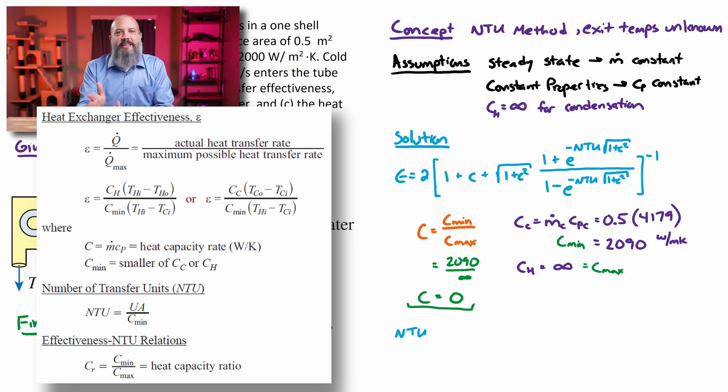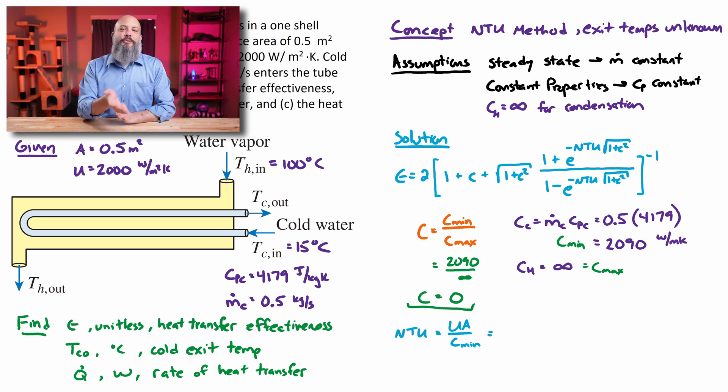So NTU, number of transfer units, is a ratio between UA and CP. Think of the heat transfer equations: M dot CP delta T and UA delta T. Those delta T terms are different. For M dot CP delta T, it's the temperatures within a stream, like inlet versus outlet. For UA delta T, you're comparing the two temperatures that are right next to each other. But NTU is a ratio of the front parts of these equations, UA versus M dot CP. And specifically, the M dot CP, whichever one is lower. NTU is going to be just a value greater than zero.